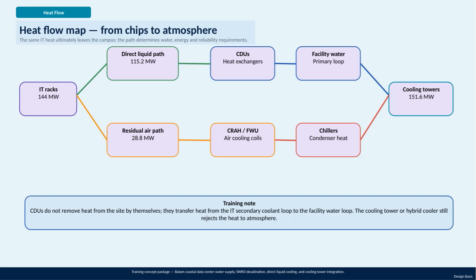Let's take a closer look at the heat flow in this data center and how the heat travels from the IT equipment all the way to the atmosphere. The total IT load is 144 megawatts, which represents the amount of heat generated by the IT racks. Out of this, about 115 megawatts are carried away through the direct liquid cooling path, which efficiently transfers heat from the IT racks using a secondary coolant loop. The remaining 29 megawatts are removed via the residual air path. This dual-path approach optimizes how heat is managed.